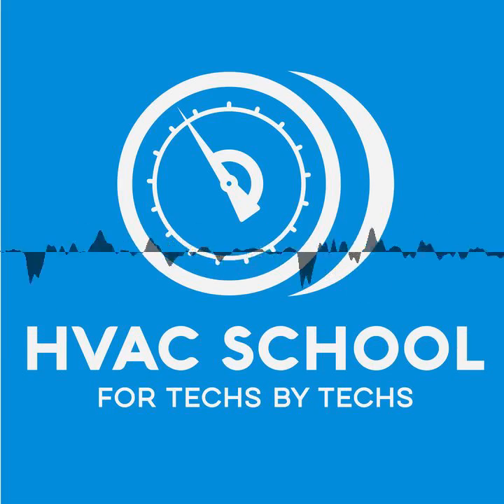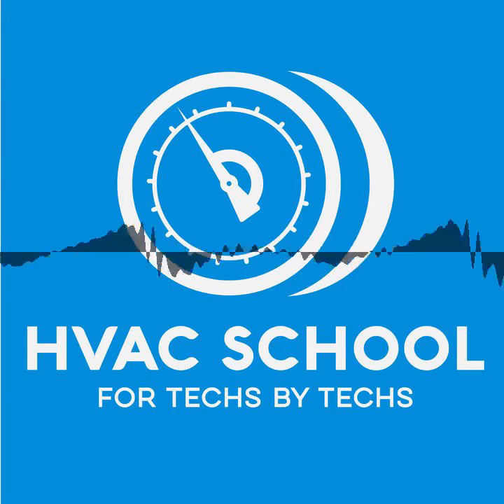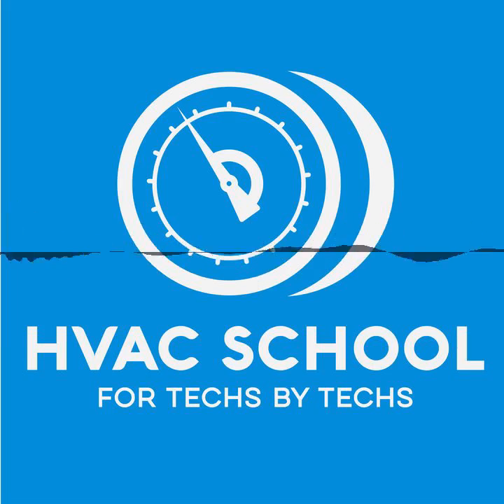But electric defrost is going to remain one of the popular choices just because it's a whole lot cheaper. Cheaper, and also there's some other considerations too. When you're using hot gas, you have to be careful to not re-inject hot gas straight back into the compressor. There's a couple different things you have to consider, in addition to the fact that you do have a little bit more expansion and contraction of the copper with hot gas. And that's something that my friend Jeremy Smith, who comes on the podcast a lot, has talked about: in grocery store refrigeration systems, you can actually get lines that move a significant distance over long expanses just because of that expansion and contraction from hot gas defrost. Is that something you've seen?